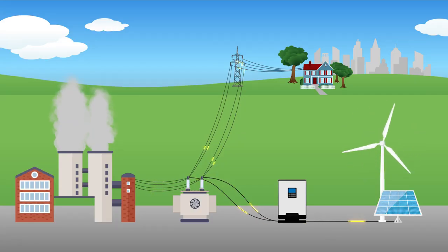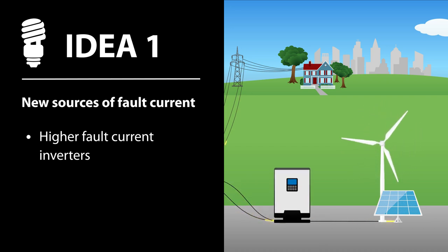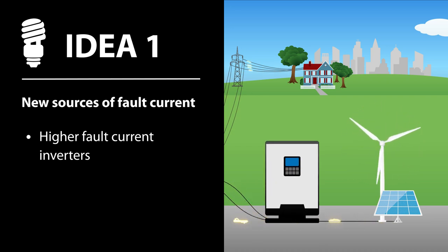If we keep the grid running the way it is now, with grid protection schemes that are based on fault current, we have a couple of options. One is to design inverters that can provide fault current. We can do this by oversizing certain components in the inverter.